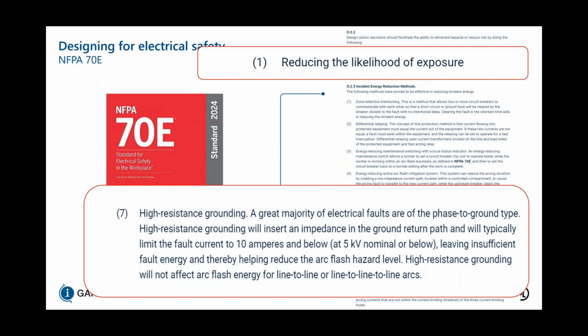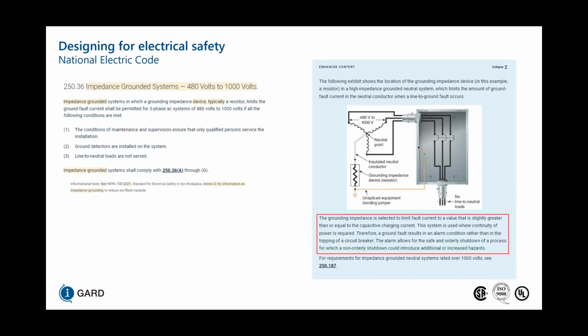The only issue with high resistance grounding is that it can't reduce the magnitude for all scenarios, particularly when there's a phase-to-phase or phase-to-phase-to-phase failure, in which the resistor at the source gets bypassed because the 2 faulted points would be circulating current between each other, growing to thousands of amps and not being limited by the resistor at the source. In that case, it's likely that the instantaneous function of your breaker is going to detect that high level of current and instantaneously trip the breaker that is affected by the ground fault and the phase-to-phase failure.